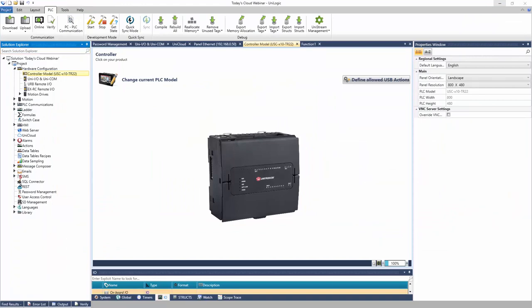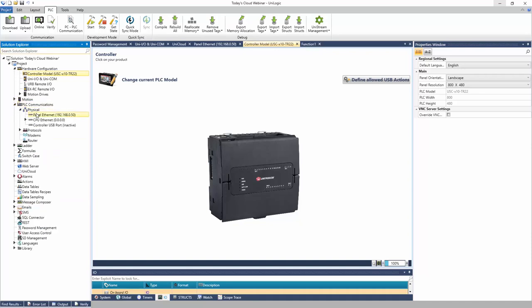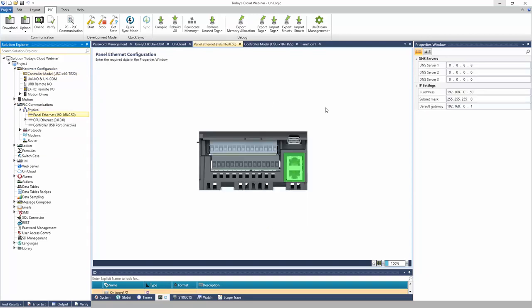Today I'm working with a USC-C10-TR22, which is the embedded cloud PLC-only model. The first steps are to put the controller on the network since it needs an internet connection. Go to PLC Communications > Physical > Panel Ethernet and assign an IP address on your local network. Additionally, define a DNS server — I'm using 8.8.8.8, Google's free DNS. The DNS is important for connecting to the cloud, translating website names to IP addresses. You can use Google's free DNS or one assigned by your IT department.